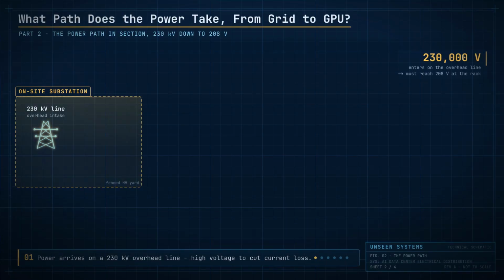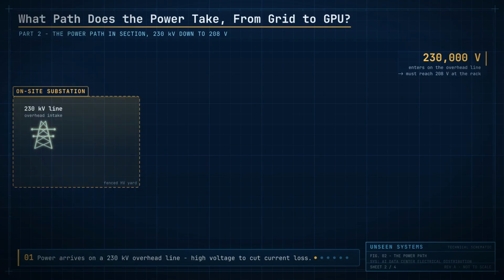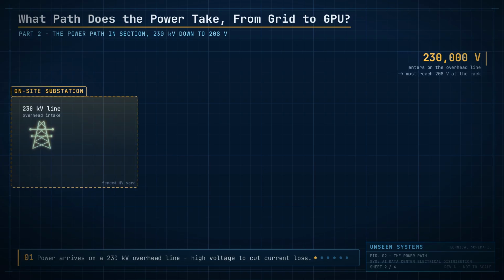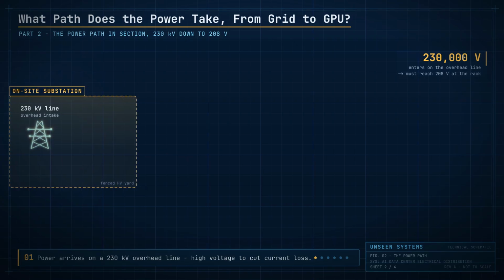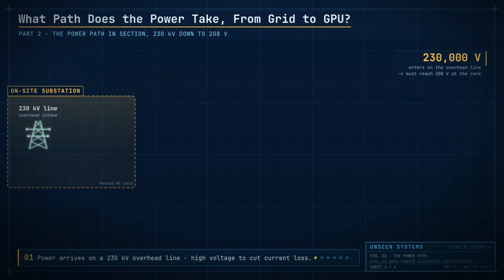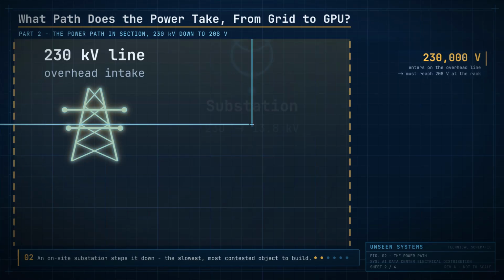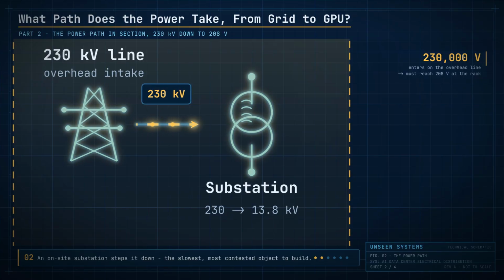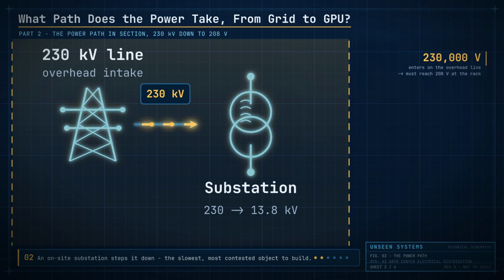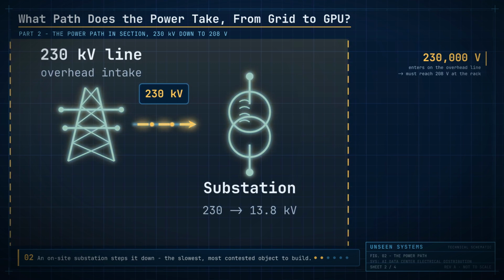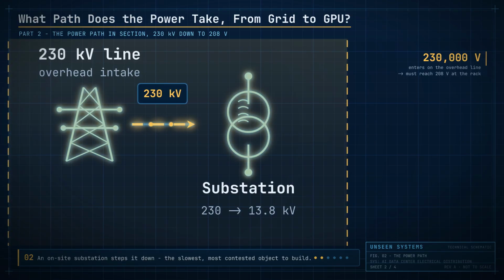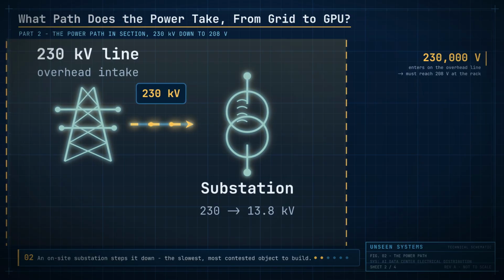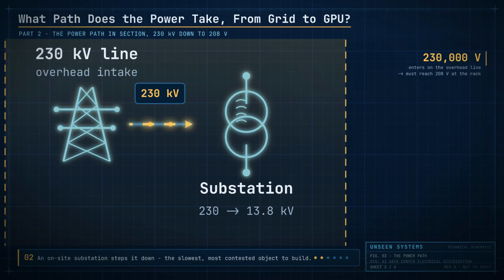So follow that power in. It does not come from a wall socket. A gigawatt campus needs its own dedicated substation right at the fence line, where a high-voltage transmission line arrives at something like 230,000 volts. Why so high? To cut the losses on the way in, and we will see exactly why once we reach the load. At the fence, that first substation steps 230,000 volts down toward around 13,800, what the industry calls medium voltage. And this single object, the substation, is the most contested, slowest to build thing on the entire site. Everything downstream lives or dies on getting it energized.